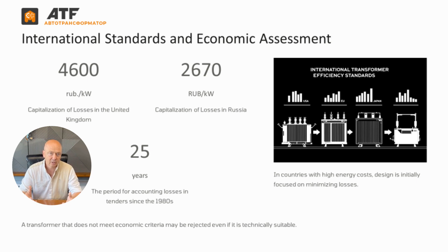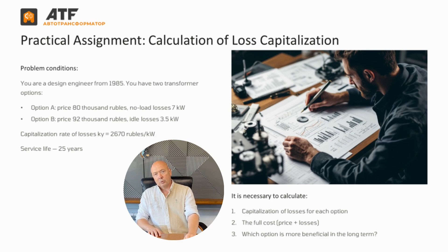Now, for a practical exercise, you are a design engineer in 1985. You have two transformer options. Option A costs 80,000 rubles and has 7 kilowatts of no-load loss. Option B costs 92,000 rubles and has 3.5 kilowatts of no-load loss. With a capitalization rate of 2,670 rubles per kilowatt and a 25-year service life, calculate the capitalized losses for each option, the total cost: purchase price plus losses. Which option is more cost-effective in the long run?